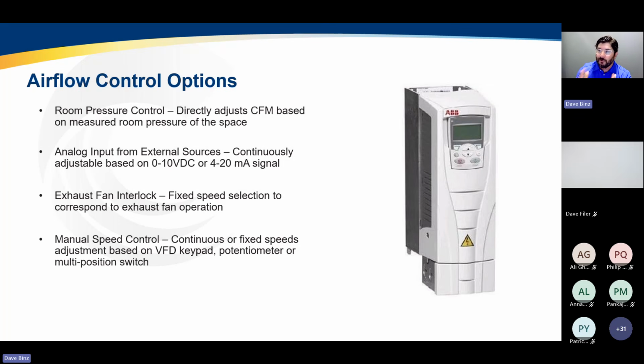But what that allows us to do is match my ventilation load to my exhaust load. So I'm not over-pressurizing the space. I'm not adding more air to the building than it would naturally breathe, which could cause building pressure problems, process problems, product quality problems, or excess energy use. So look at how you can modify your airflow control. What we most often do is implement VFDs on our fans to control airflow. We're going to make sure that we can modulate that airflow based on either building pressure, or maybe some other types of process signals. That's just trying to balance my airflow from exhaust and makeup air.